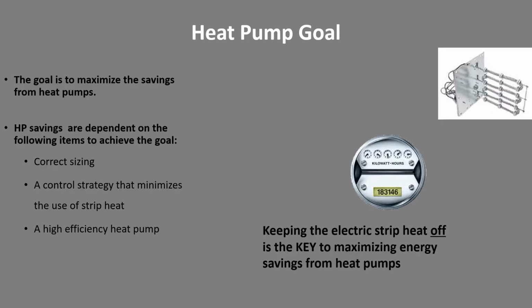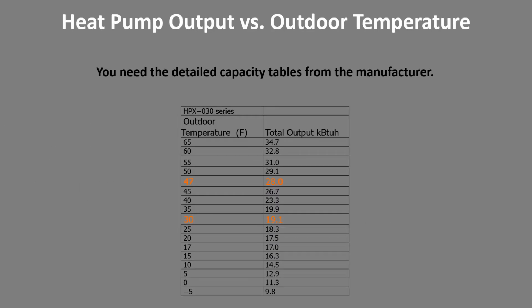Heat pump goal. The heat pump goal in PTCS is to maximize the savings from heat pumps. In order to do this, we need correct sizing, a control strategy that minimizes the amount of strip or auxiliary heat, and a high efficiency heat pump. Keeping the strip heat off is the key to maximizing energy savings. Say a 3-ton heat pump draws about 3 kW and there's 15 kW worth of backup. Boy, as soon as that 15 kW backup comes on, you go from 3 kW all the way up to 18 kW. You basically increase the energy used by a factor of 6 when that happens.